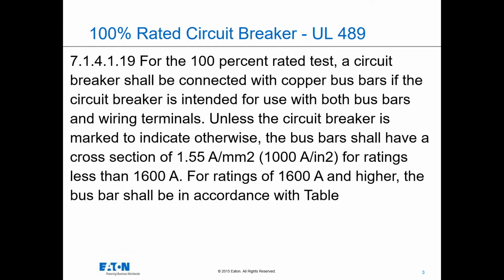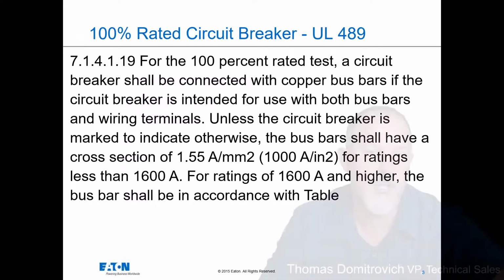For the 100% rated test, a circuit breaker shall be connected with copper bus bars if the circuit breaker is intended for use with both bus bars and wiring terminals. Unless the circuit breaker is marked to indicate otherwise, the bus bars shall have a cross section. So they're telling you the size of the bus bars, and it has to be copper. Where does it say copper? Have a cross section for ratings. A circuit breaker shall be connected with copper bus bars. So it has to be copper.